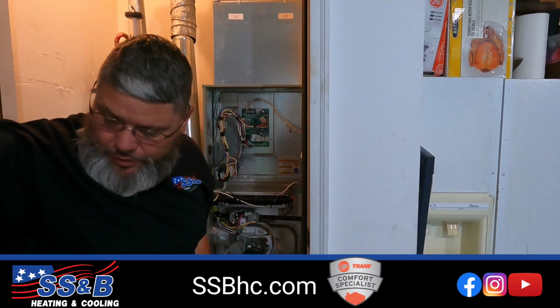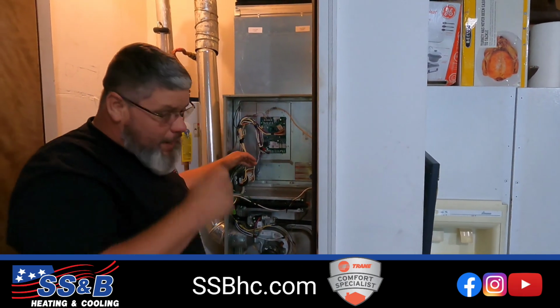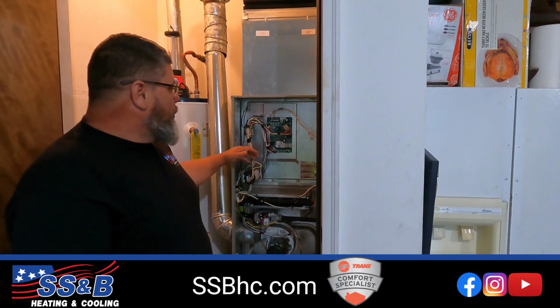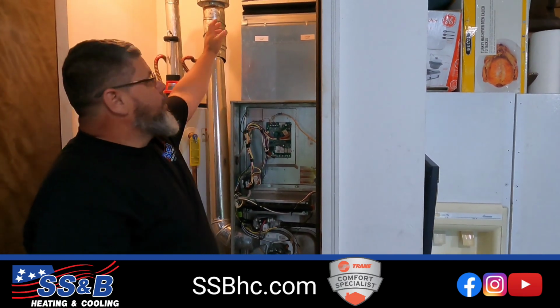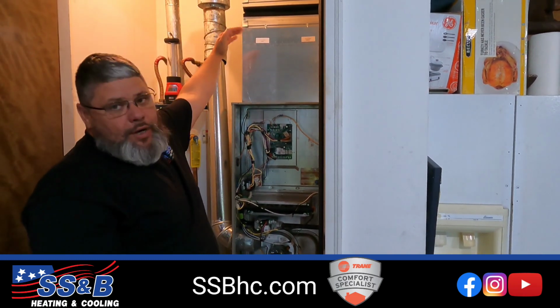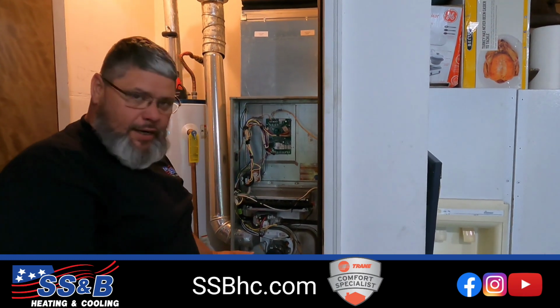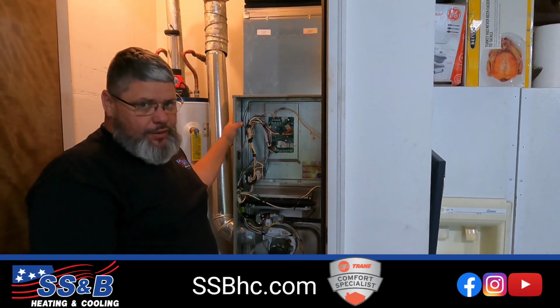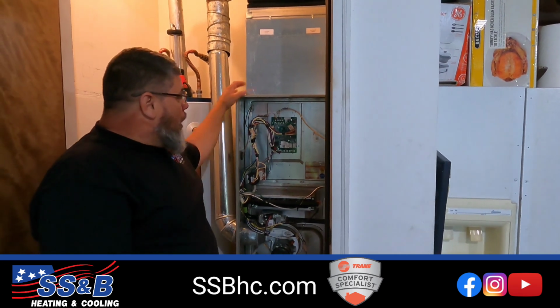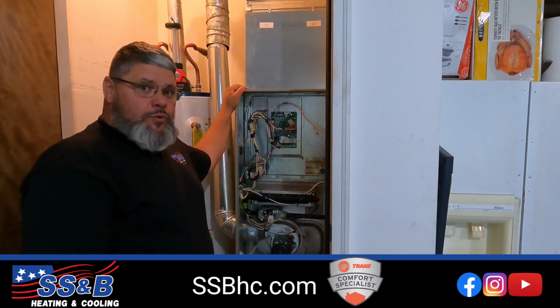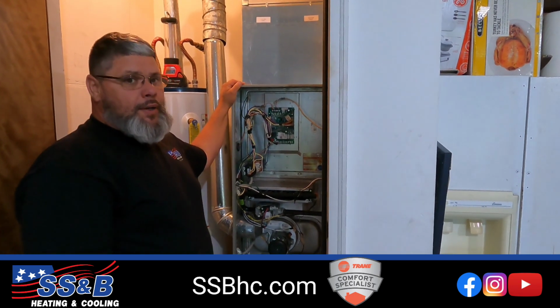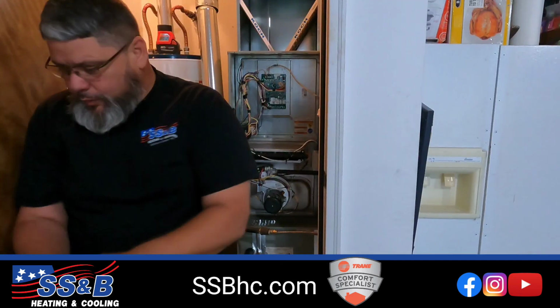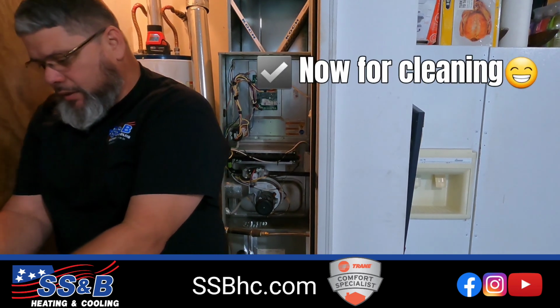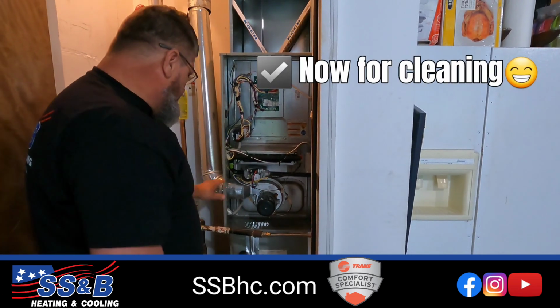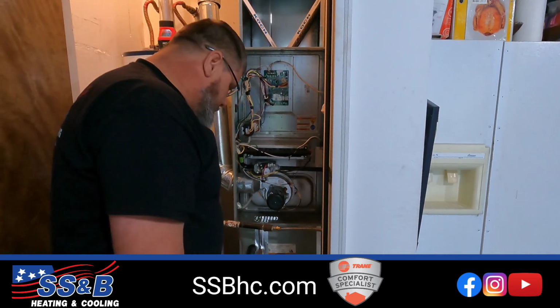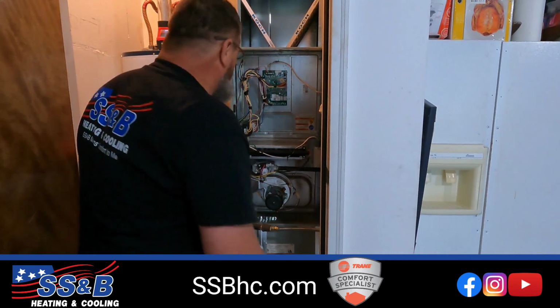All right, once all that is done, then we'll start the system back up again. We will take what's called a temp rise, which is the difference in temperatures between the return air that's pulling in and the heated air that's blowing out. We always make sure that's set according to manufacturer. Also, at that time we check the amp draw on the blower to make sure that it's not overamping, and then make sure it's within range. Once we get all of that done, the final thing is to actually clean the furnace interior cabinet with a shop vac so that it's all cleaned up.